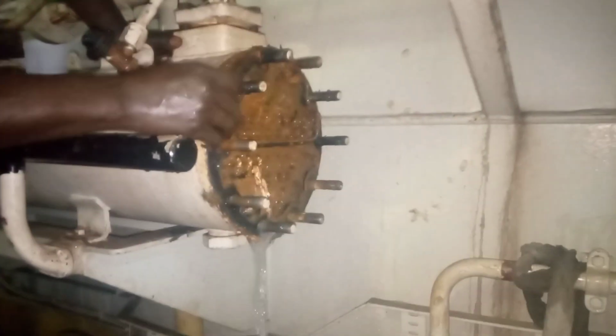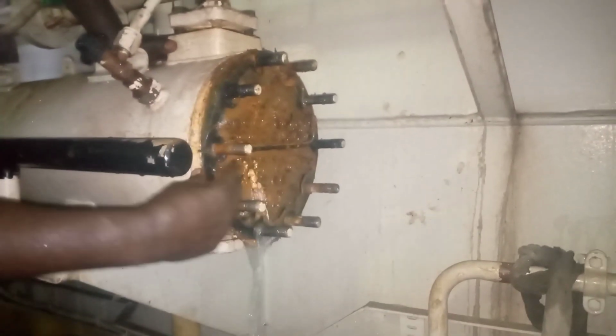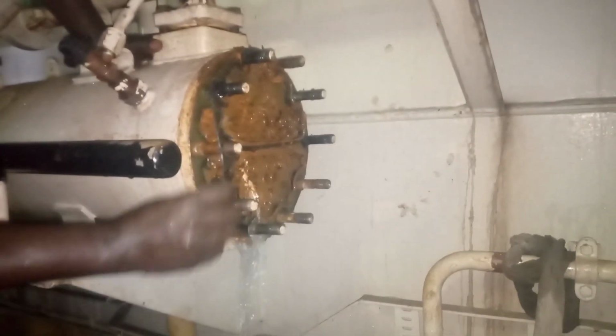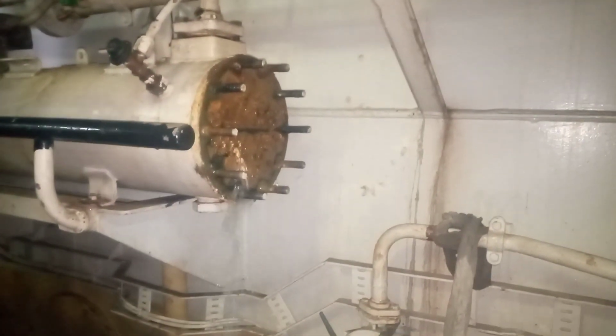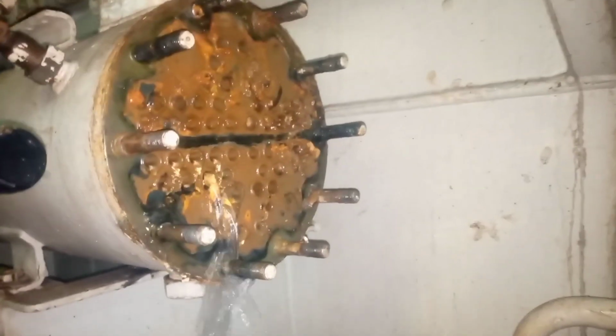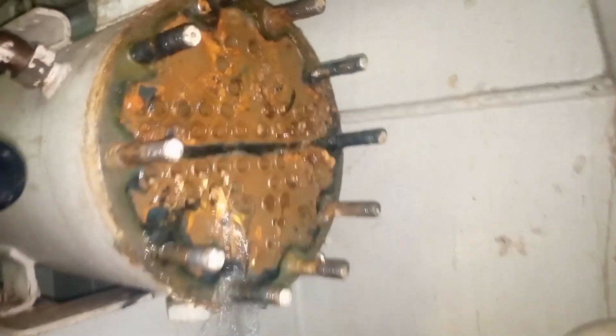After removing the closing lid, what followed was the removal of the rubber gasket, which provides maximum seal to prevent leakage of the seawater. And as you can see, corrosion had really occurred, and our goal was to remove these corroded materials and make sure that the heat exchanger was not blocked and it was as clean as a whistle.